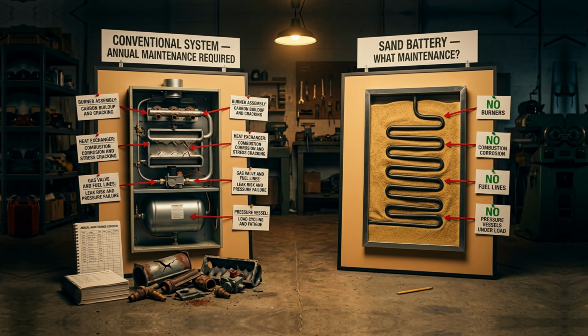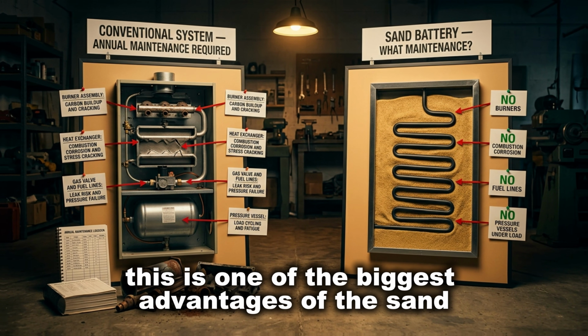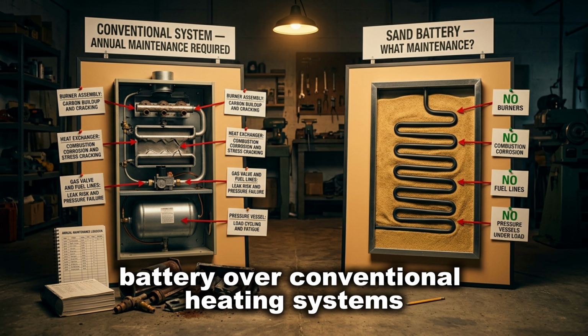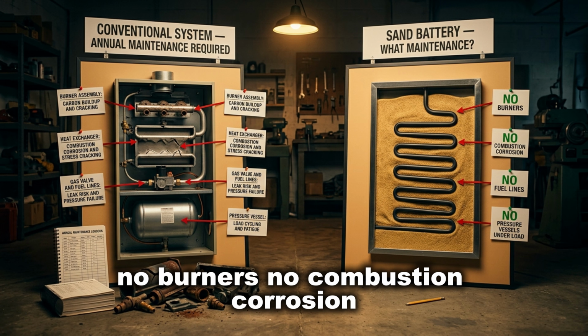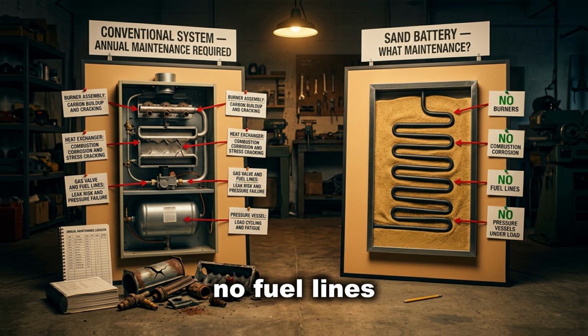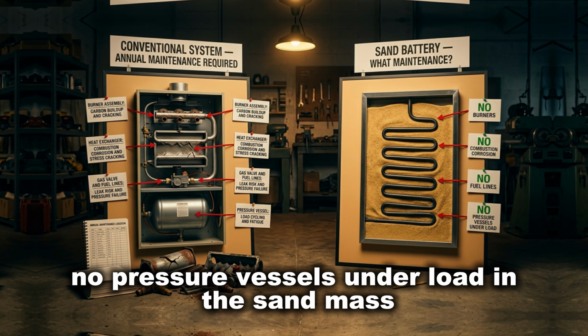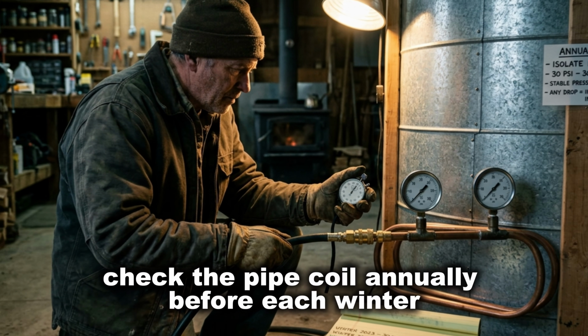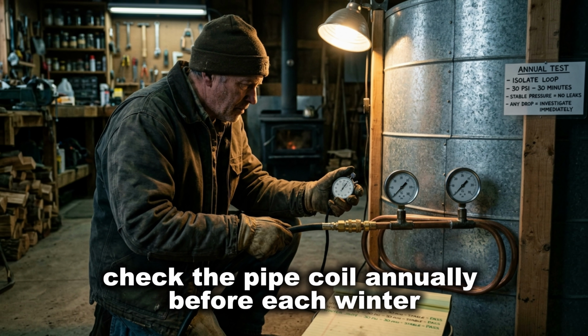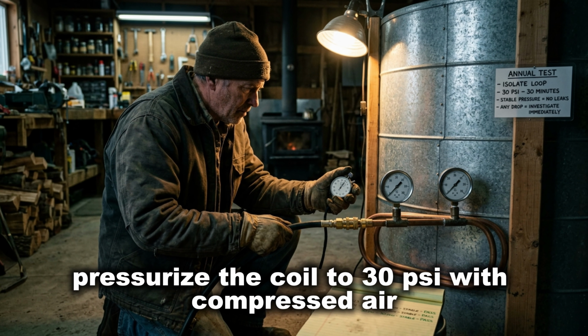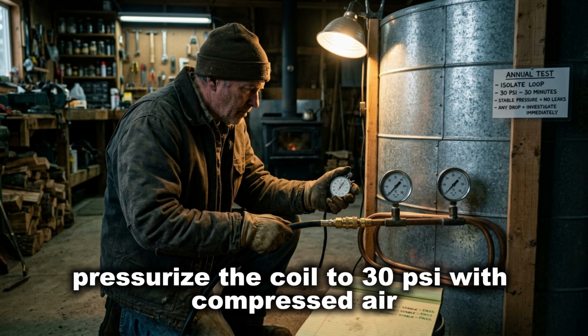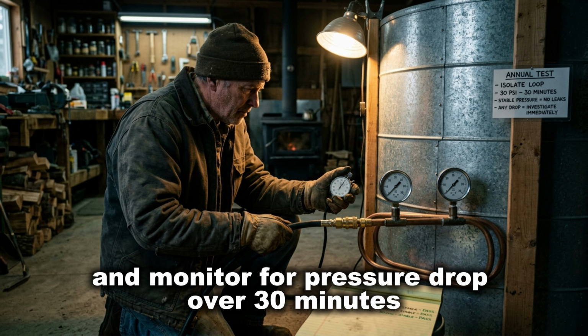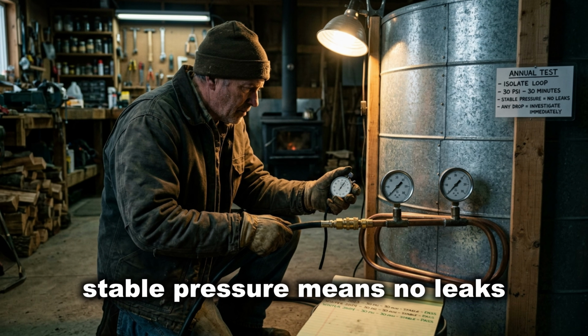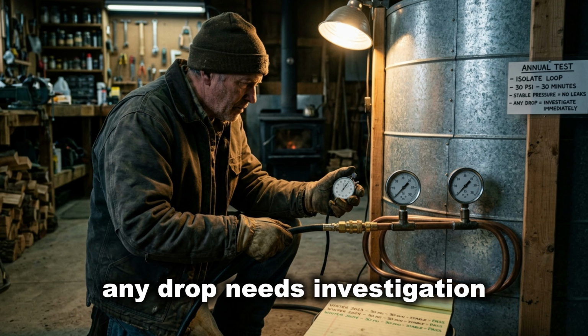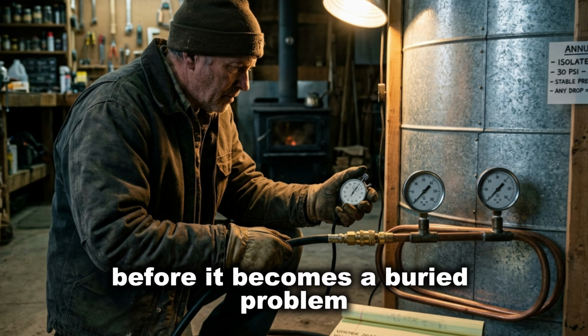On maintenance, this is one of the biggest advantages of the sand battery over conventional heating systems. No burners, no combustion corrosion, no fuel lines, no pressure vessels under load in the sand mass. Check the pipe coil annually. Before each winter, isolate the battery loop, pressurize the coil to 30 psi with compressed air, and monitor for pressure drop over 30 minutes. Stable pressure means no leaks. Any drop needs investigation before it becomes a buried problem.